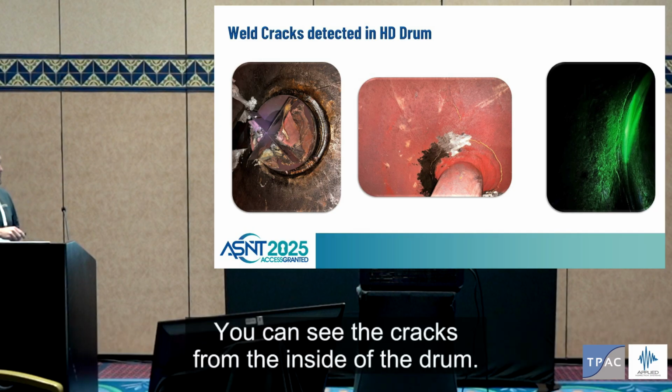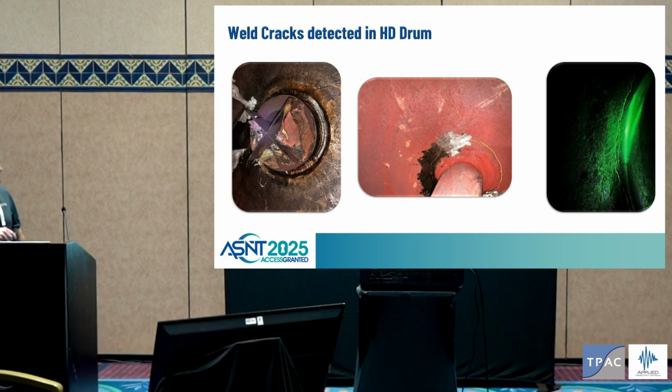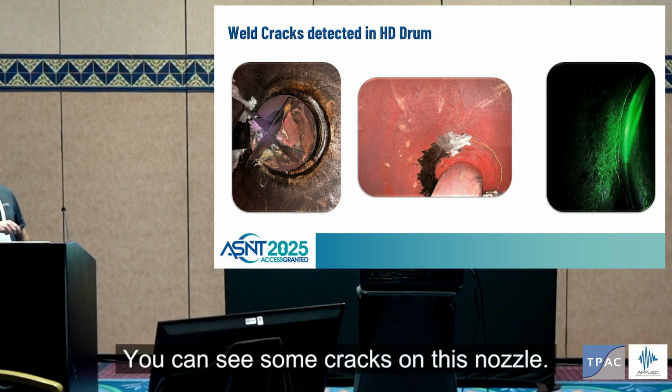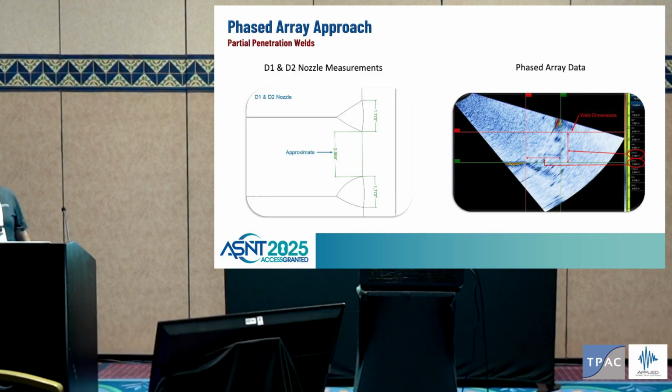So this is just some images. You can see the cracks from the inside of the drum. And this is a little repair weld here that they put in. You can see some cracks on this nozzle.